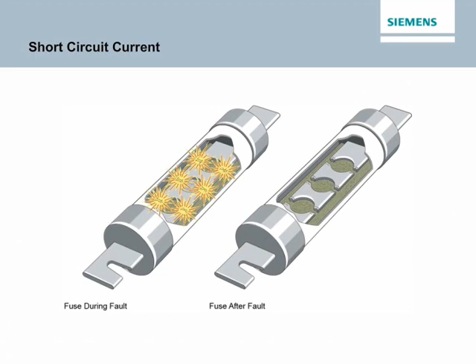Non-time delay fuses, often called fast-acting fuses, provide excellent short circuit protection. However, short duration overloads, such as motor starting current, may cause nuisance openings of non-time delay fuses. For this reason, they are best used in circuits not subject to large current surges. Non-time delay fuses usually hold 500% of their rating for approximately 1/4 of a second, after which the current carrying element melts. This means that these fuses should not be used in motor circuits, which often have starting currents greater than 500% and lasting longer than 1/4 of a second.